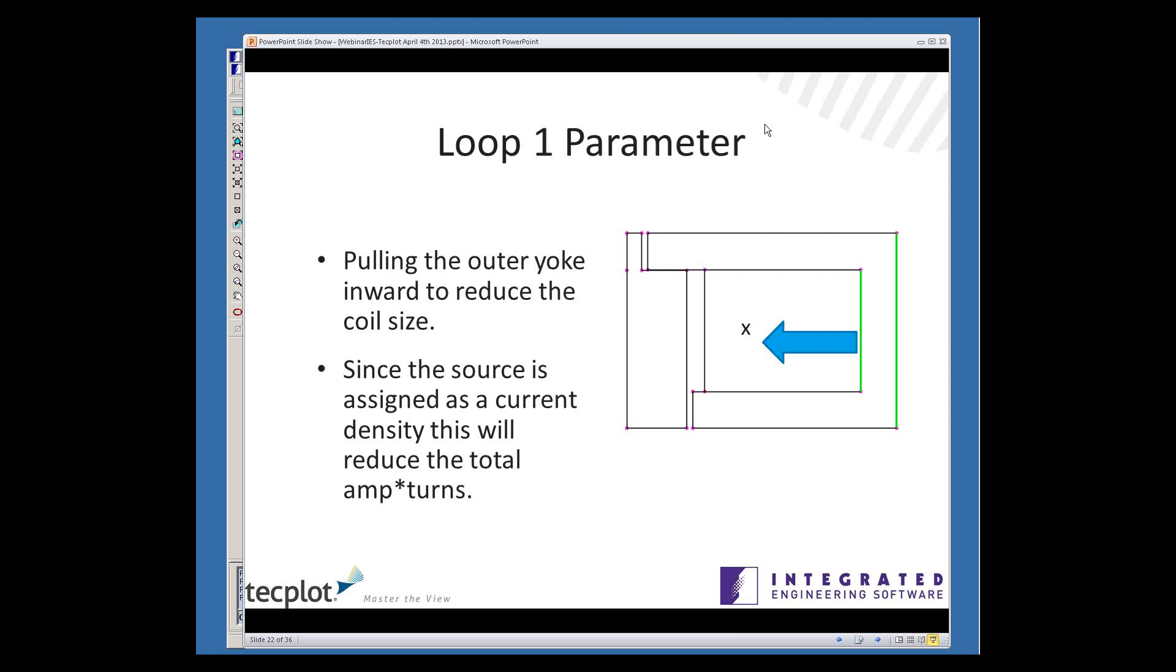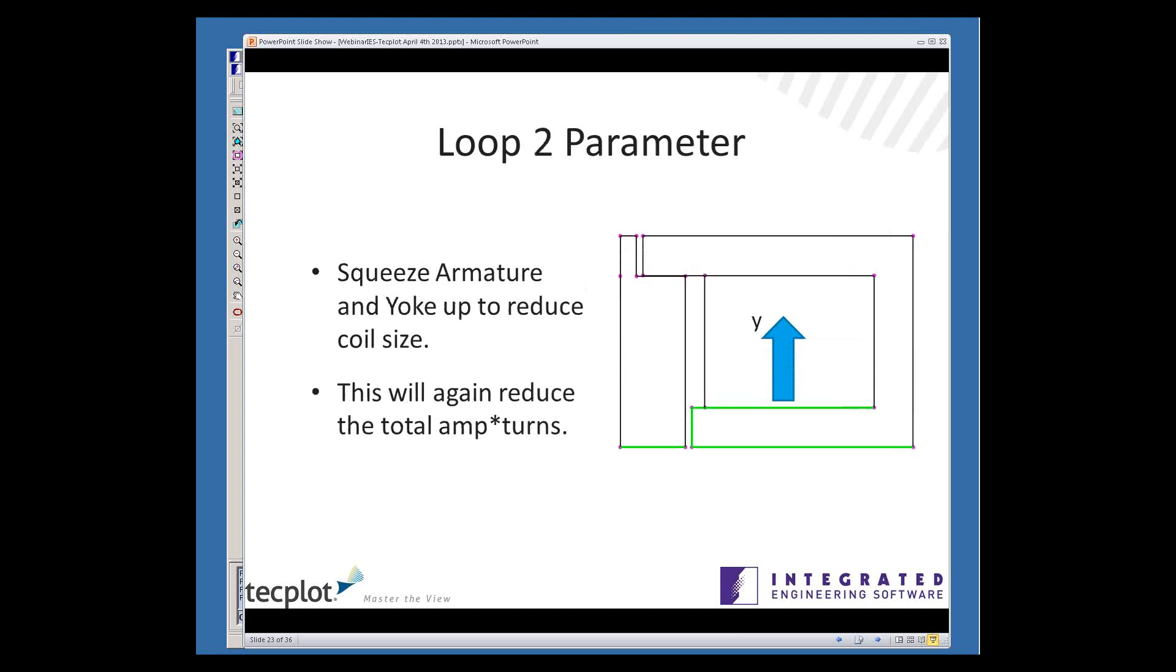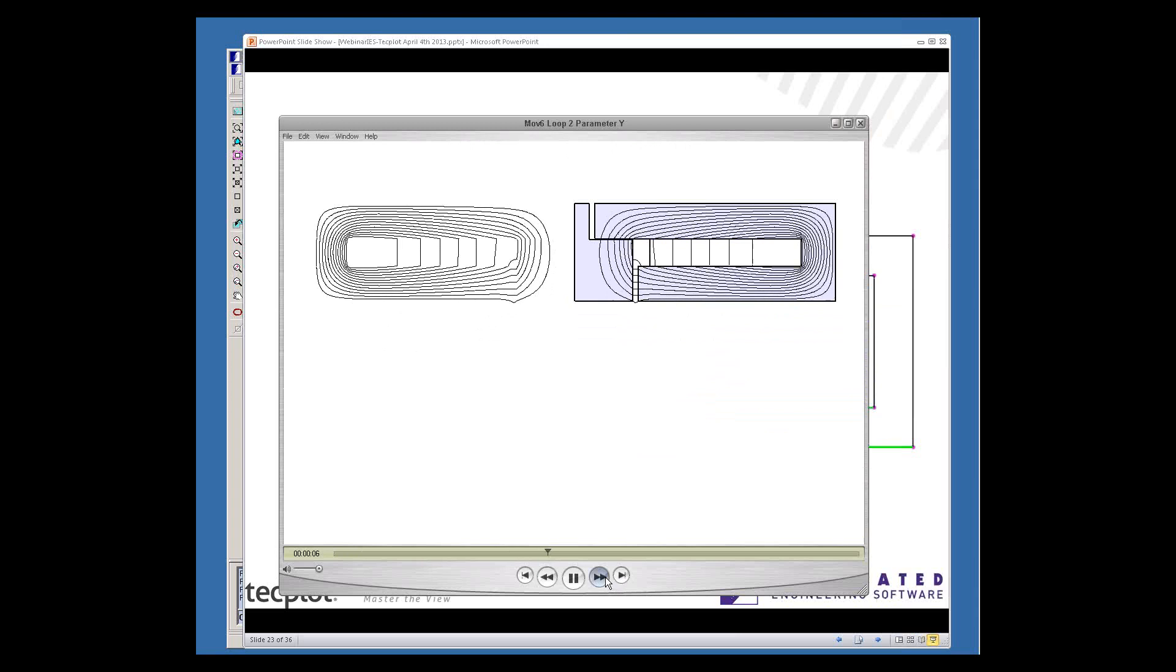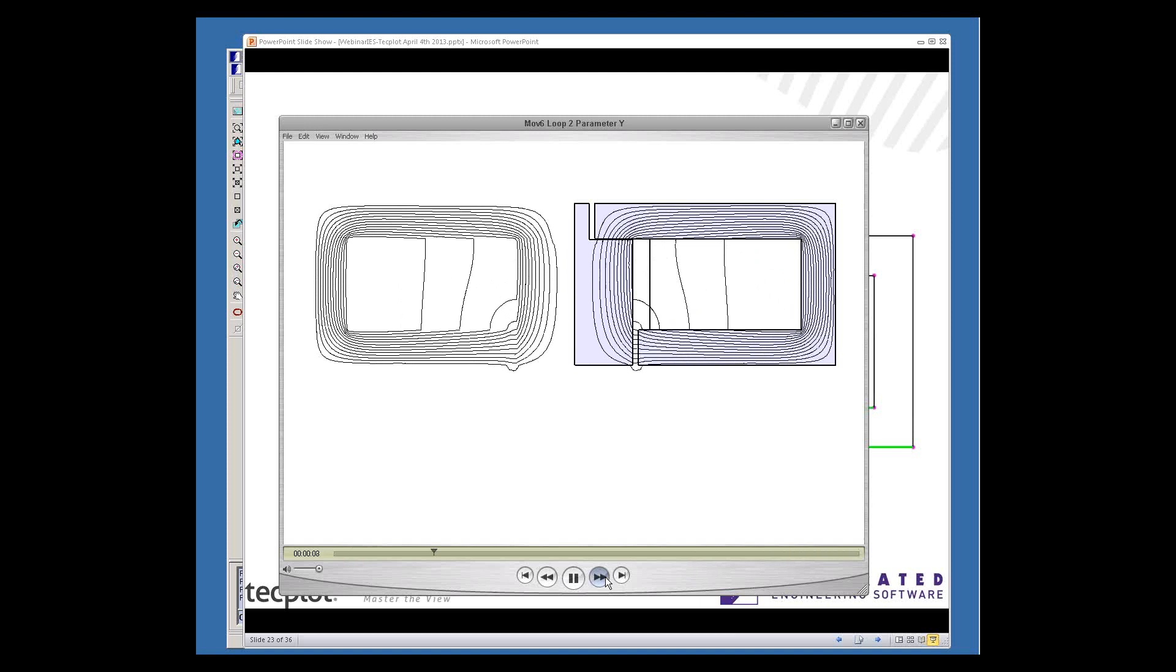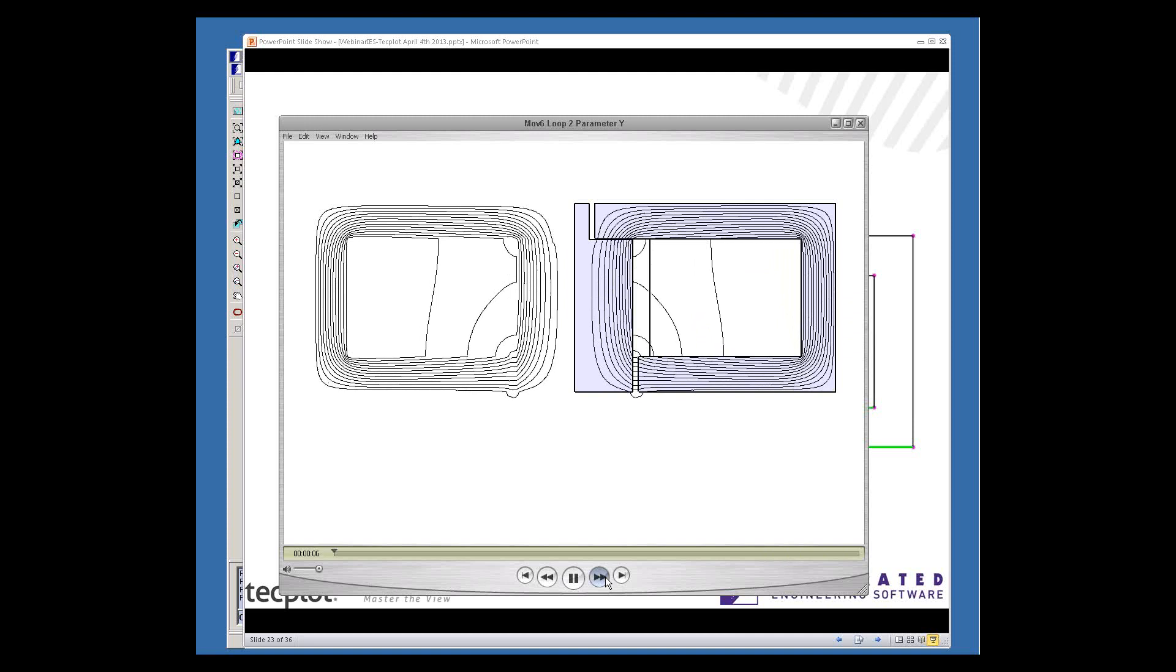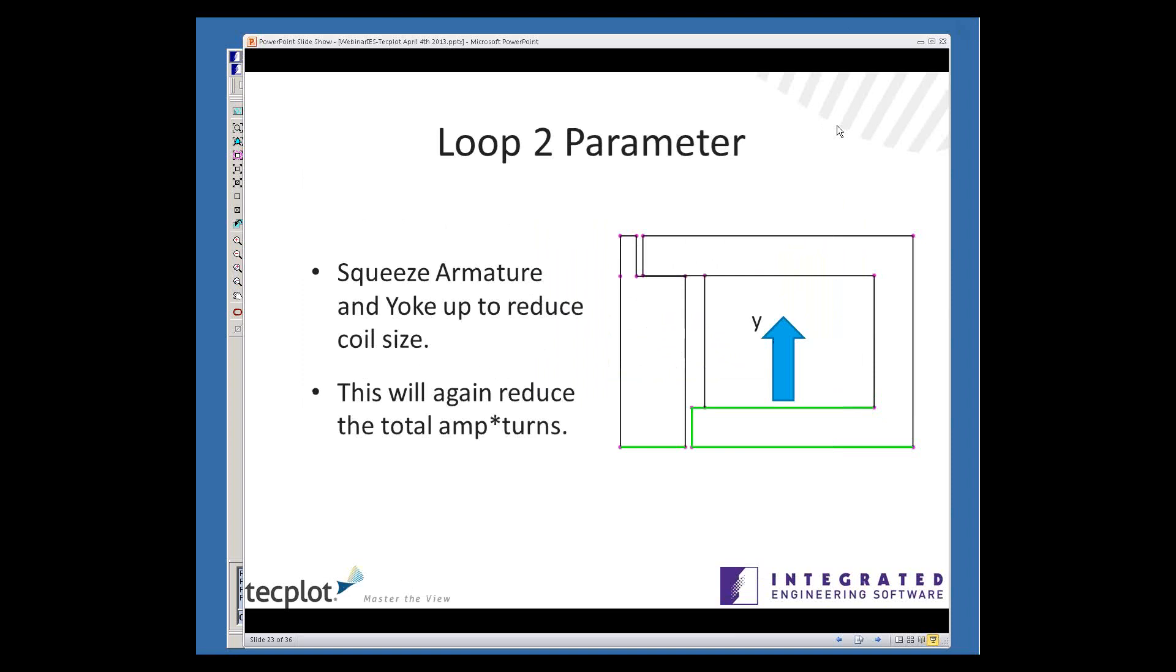Loop two will do something almost identical, but we'll compress it vertically. We'll take the lower section of the yoke and move it upward. And that, again, reduces the number of amp turns, total amp turns that you have for creating a hold-down force, and it also reduces the weight of the yoke. It looks excessively compressed, but you have to remember that these are going to be nested loops, these variables, all the ones that you're seeing are going to change in an integrated fashion.